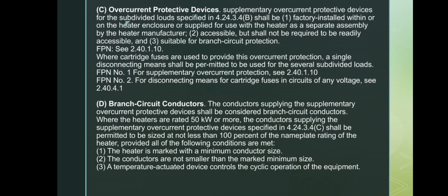D. Branch circuit conductors. The conductors feeding the supplementary overcurrent devices are treated as branch circuit conductors. For heaters 50 kilowatts or larger, the conductors may be sized at not less than 100% of the nameplate rating if all these conditions are met. First, the heater is marked with a minimum conductor size. Second, the conductors are not smaller than that minimum size. Third, a temperature-controlled device cycles the heater's operation.